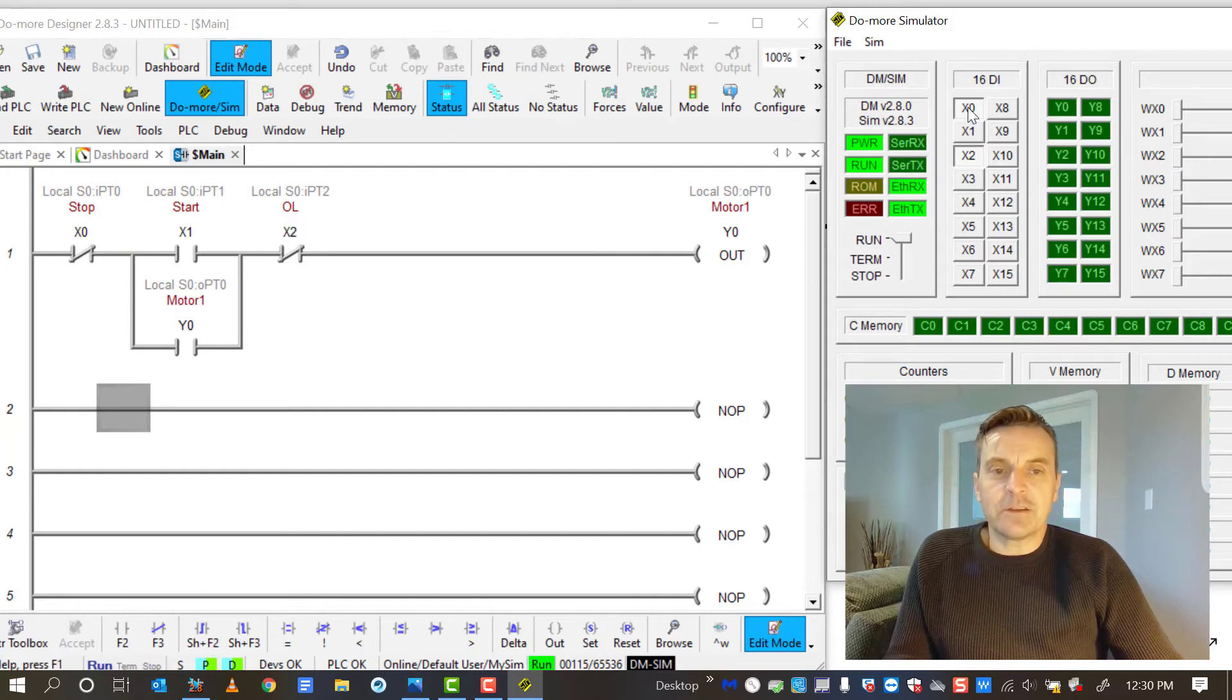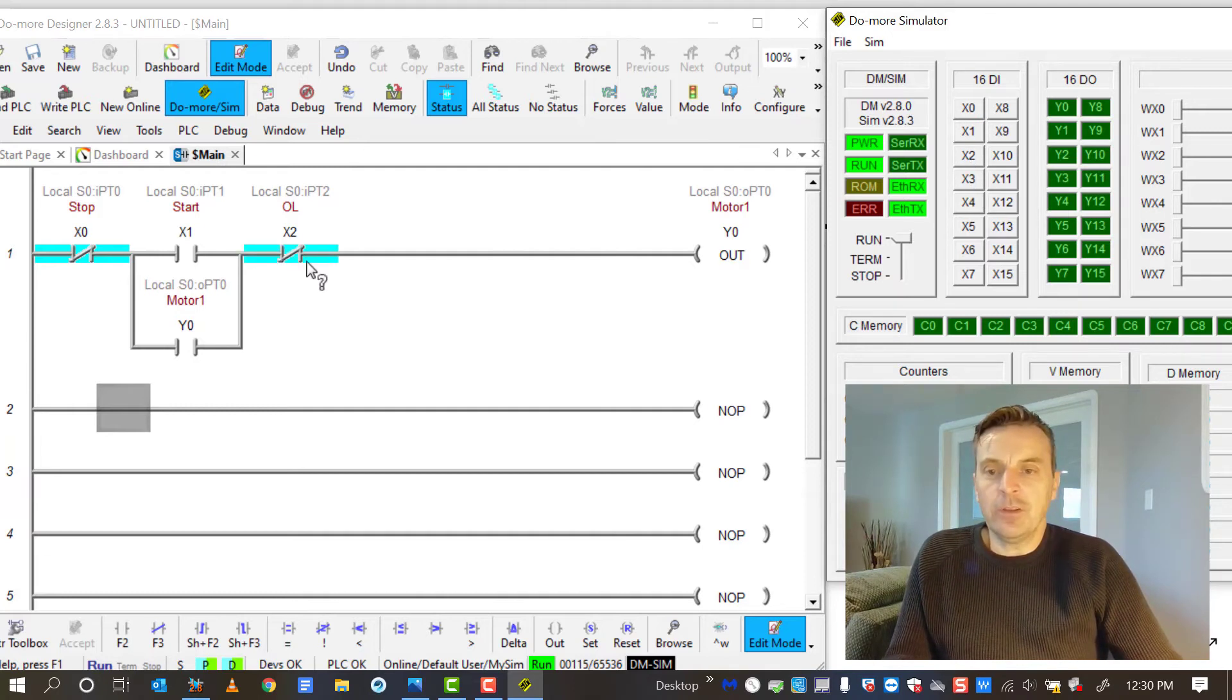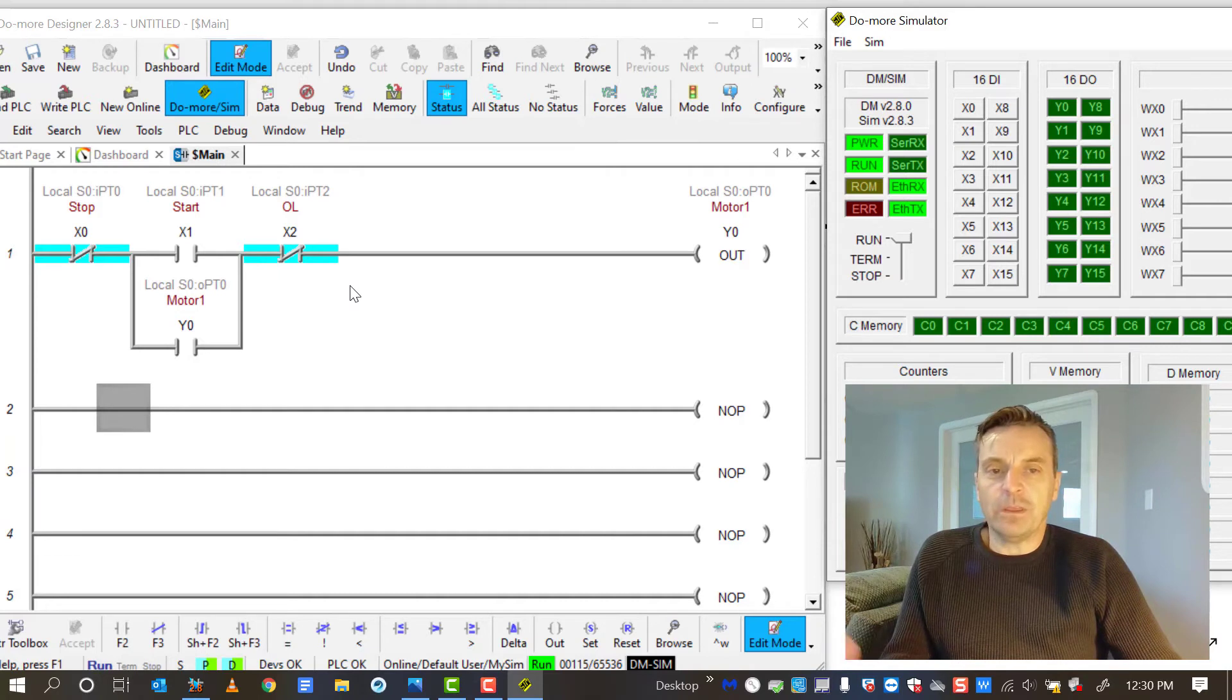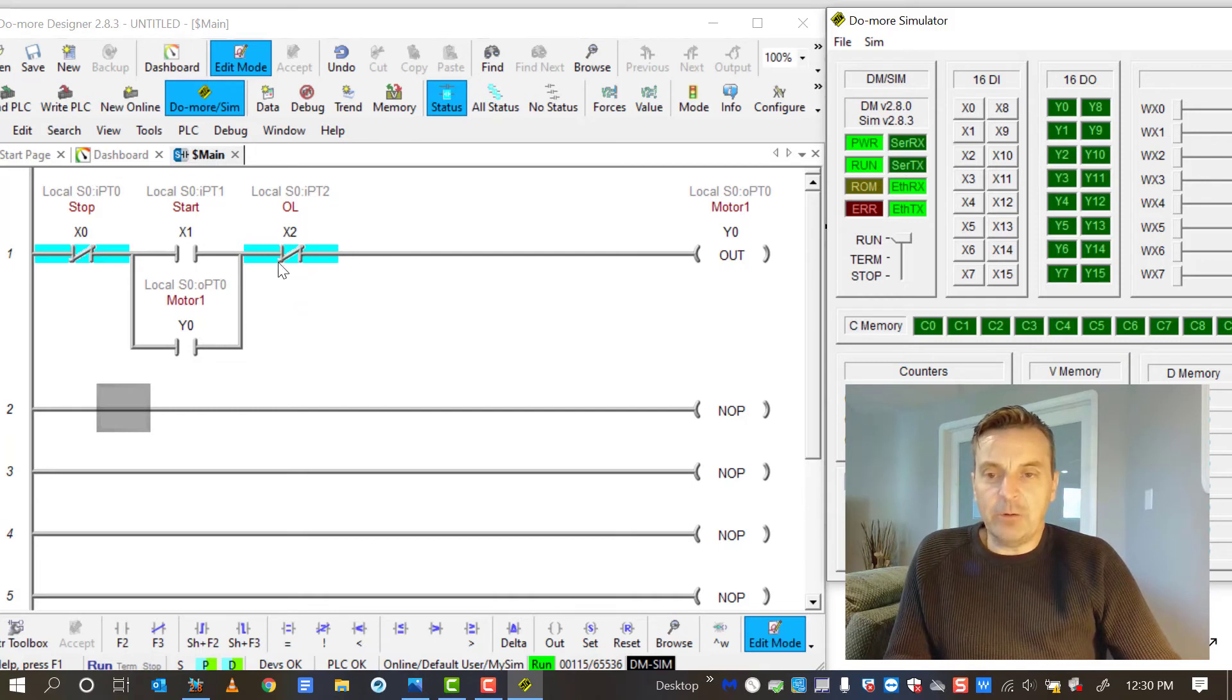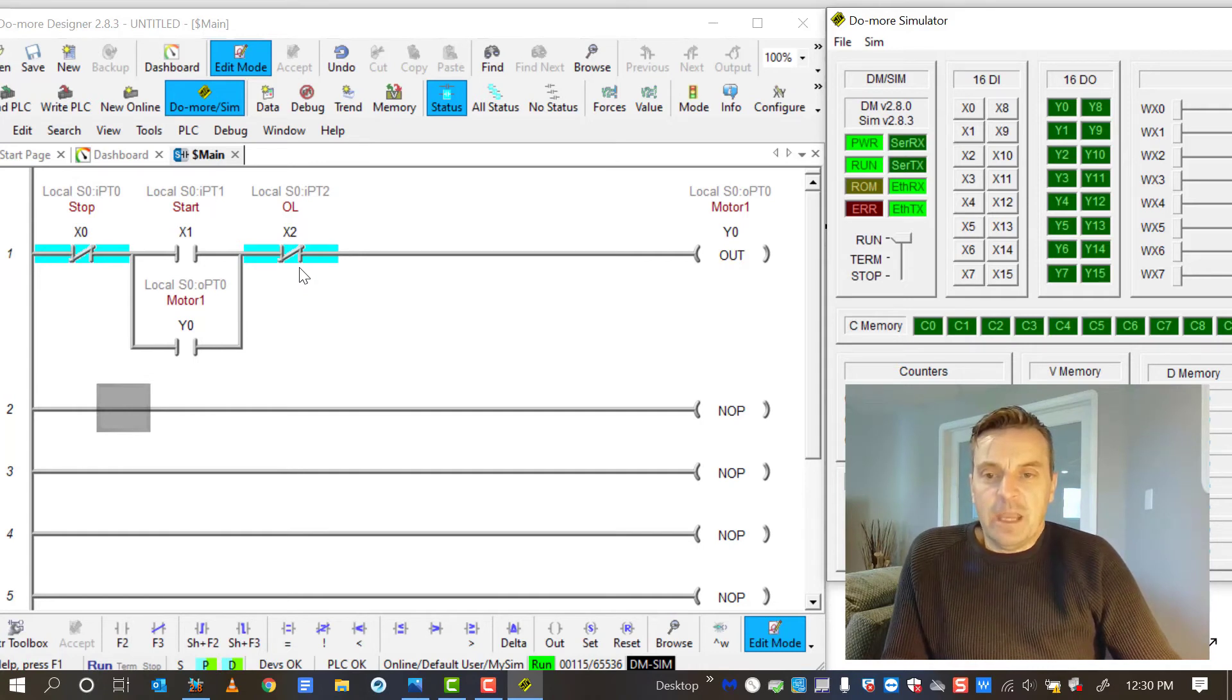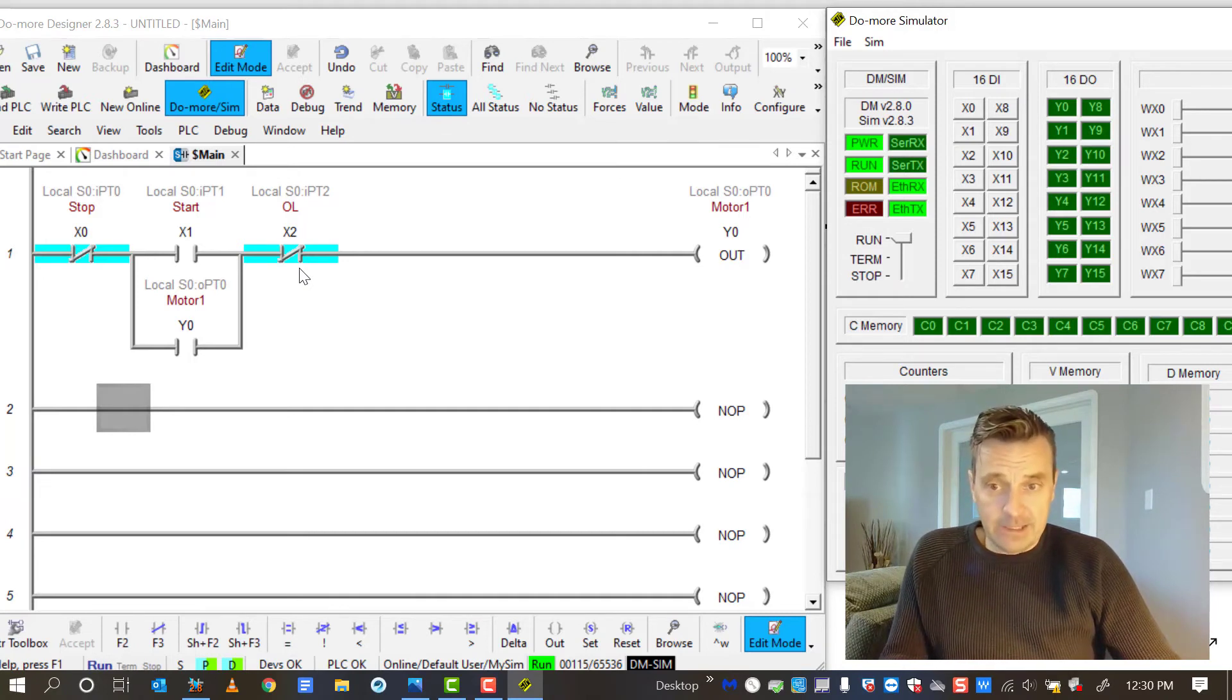So the only way to get this to start is to actually have an open button for the stop and an open contact for the overload. Even though the instruction said that these were normally closed, it just doesn't jive with how we think of contacts out in the field, because they really aren't contacts, they're instructions. And it would be better if they actually said in this instruction here and called it a different name, maybe go and look for a zero on the field device. I know that's a long name, but essentially that's what it's looking for.